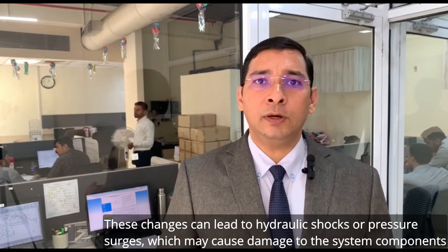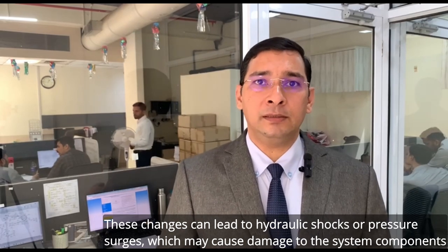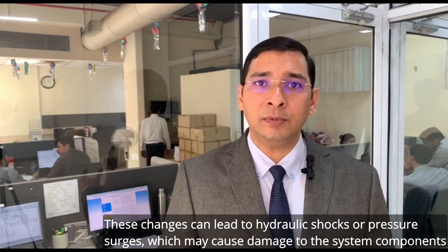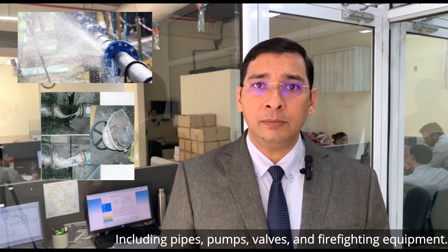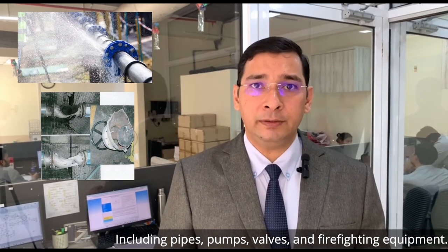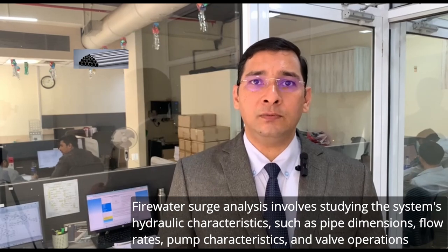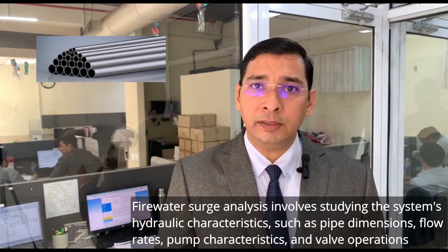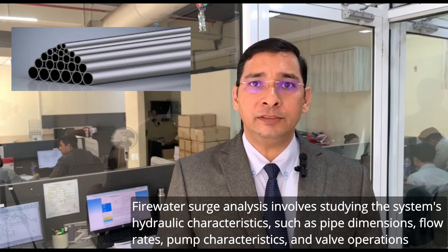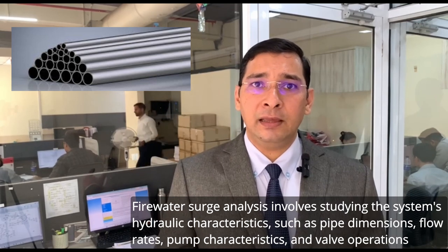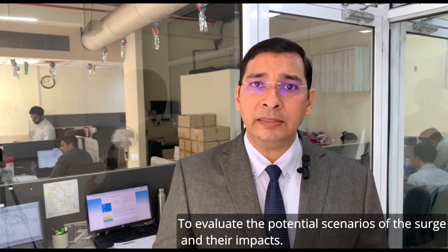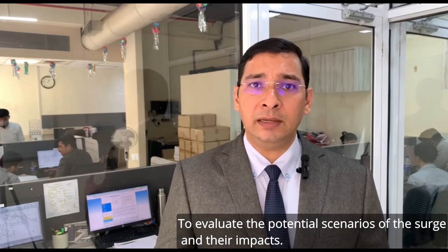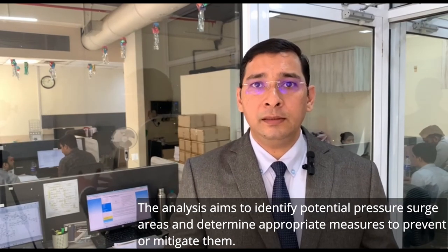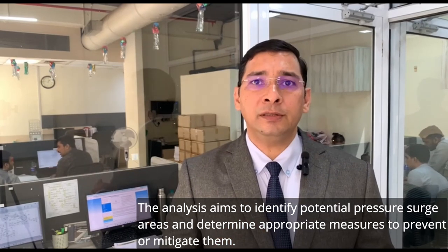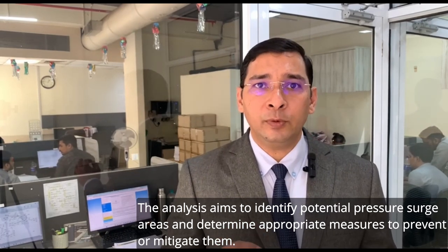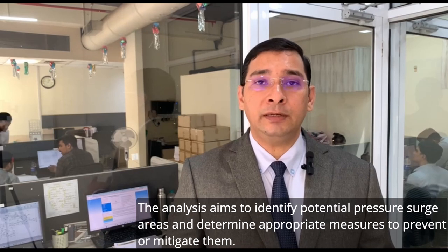These changes can lead to hydraulic shocks or pressure surges, which may cause damage to the system components, including pipes, pumps, valves, and firefighting equipment. Firewater surge analysis involves studying the system's hydraulic characteristics such as pipe dimensions, flow rates, pump characteristics, and valve operations to evaluate the potential scenarios of the surge and their impacts. The analysis aims to identify potential pressure surge areas and determine appropriate measures to prevent or mitigate them.